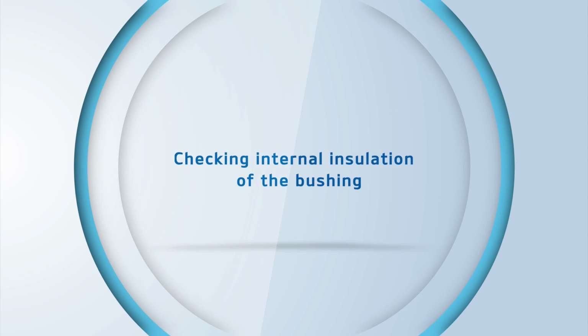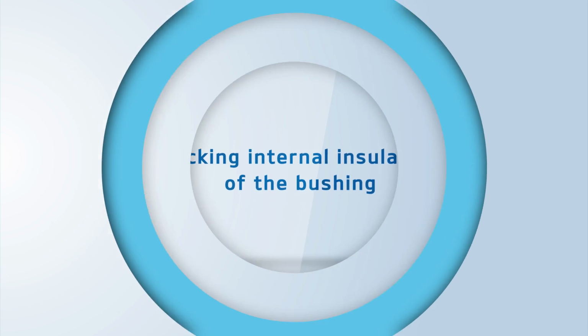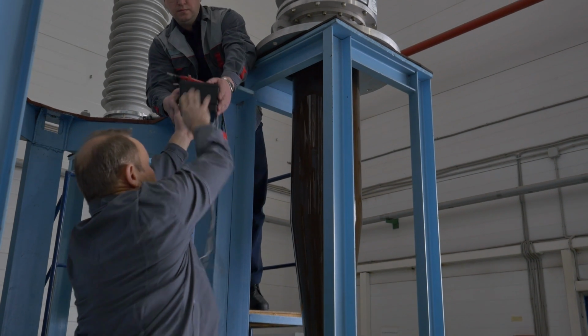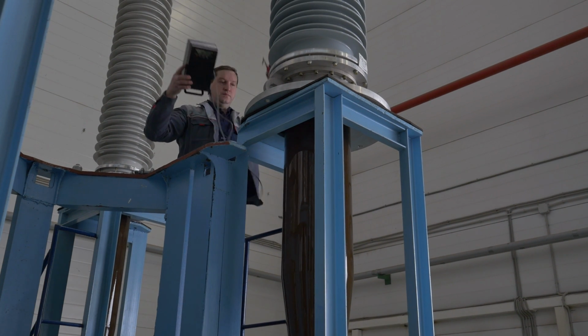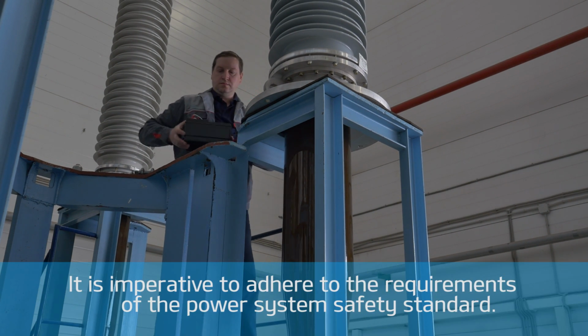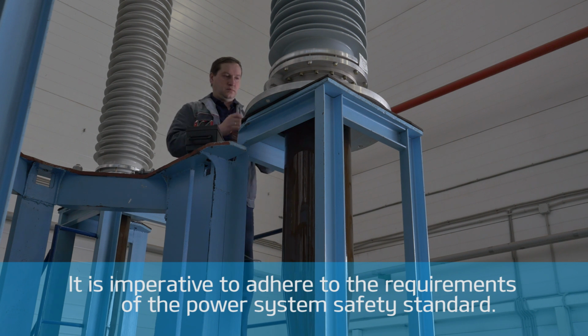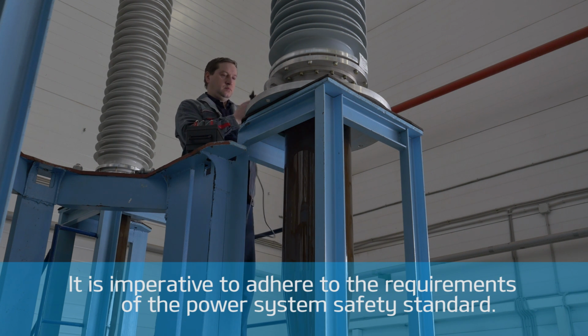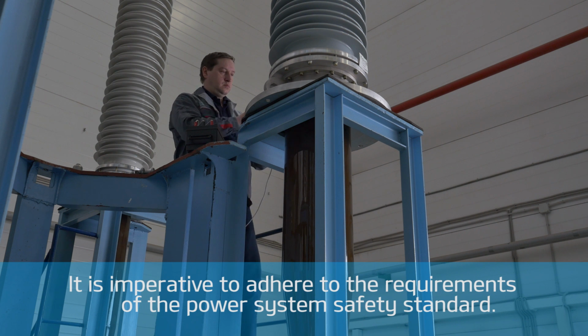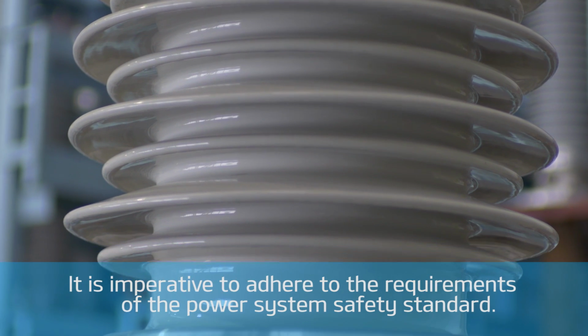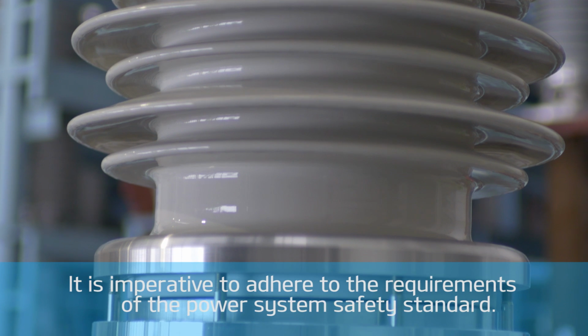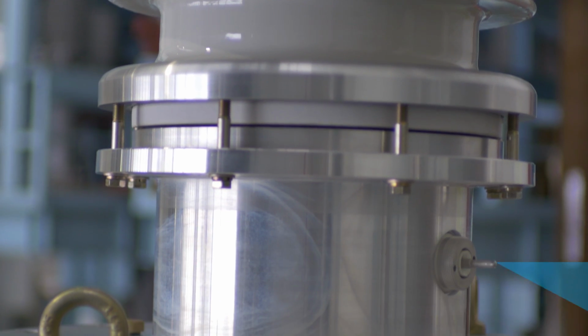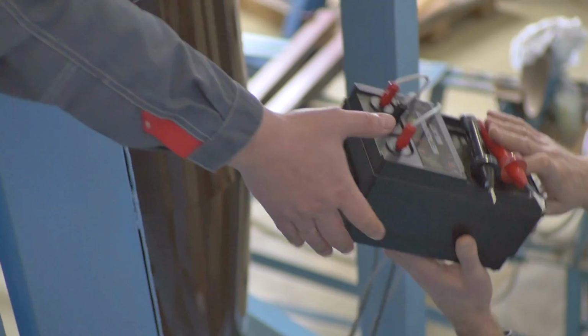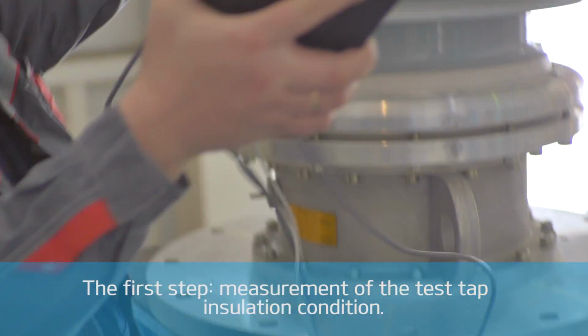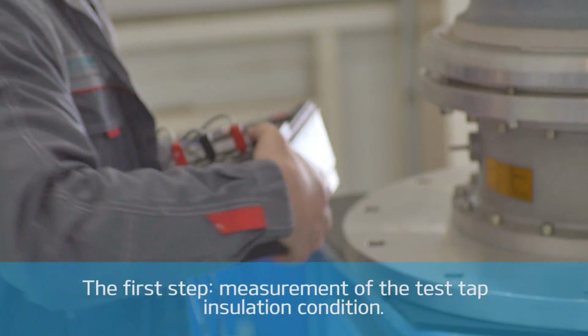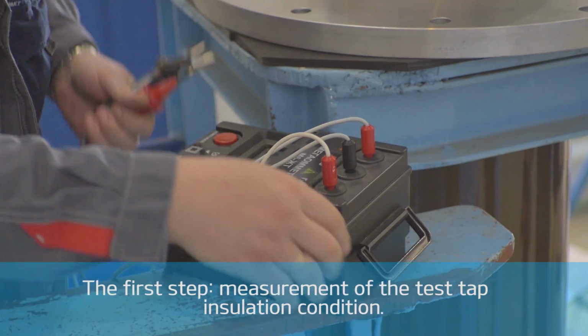Checking the internal insulation condition of the bushing. Perform the measurements on the bushing. It is imperative to adhere to the requirements of the power system safety standard, while taking electrical measurements in order to evaluate the technical condition of a bushing. There are several stages to complete measuring of the internal insulation condition in a high-voltage bushing. The first step. Take a measurement of the test tap insulation condition.